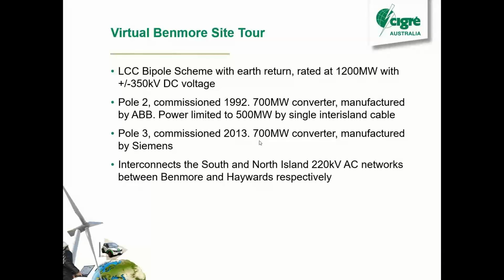So Benmore, the scheme in New Zealand, is the LCC bipolar scheme with earth return, rated at 1200 megawatts, plus or minus 350 kV. Our older pole 2 was commissioned in 92. That's 700 megawatts ABB, but the power is limited to 500 megawatts by a single cable over the Cook Strait. Pole 3 was commissioned in 2013. That's a 700 megawatt converter manufactured by Siemens. And we've got 220 kV AC at both the South and the North Island that it connects between.